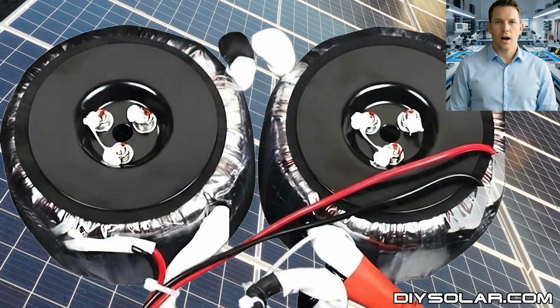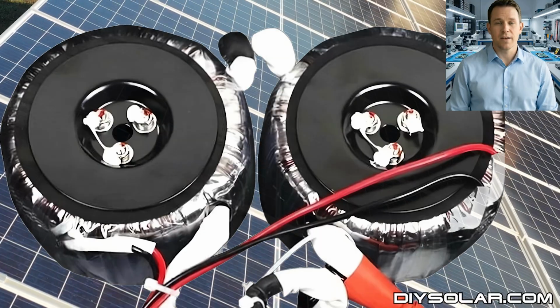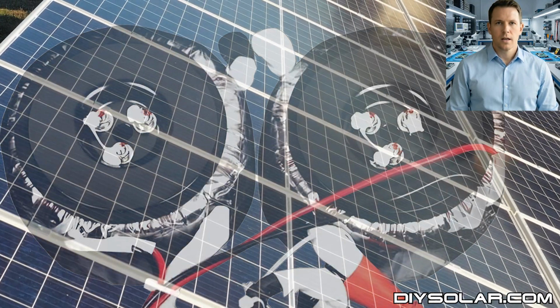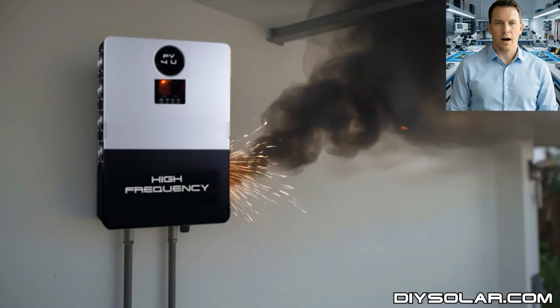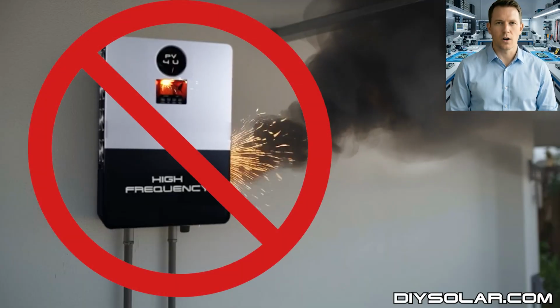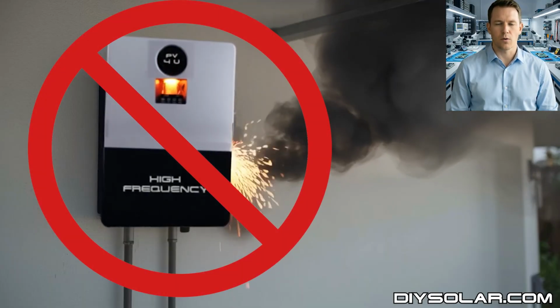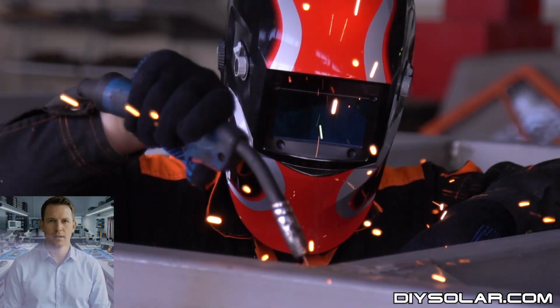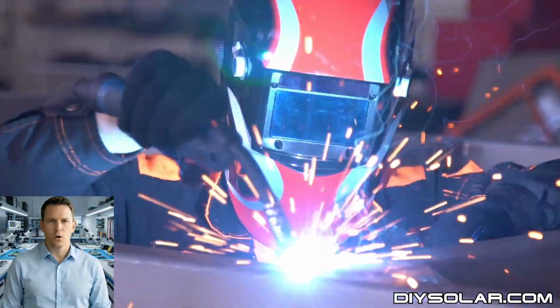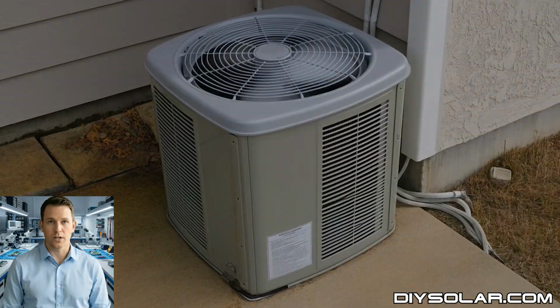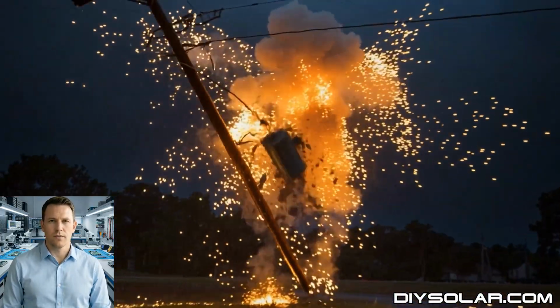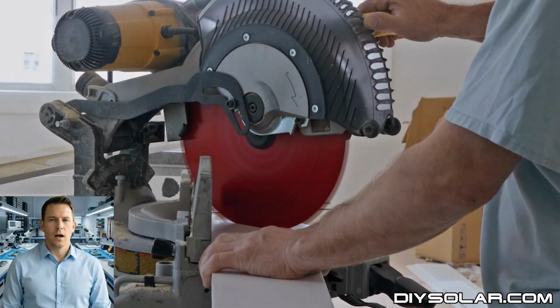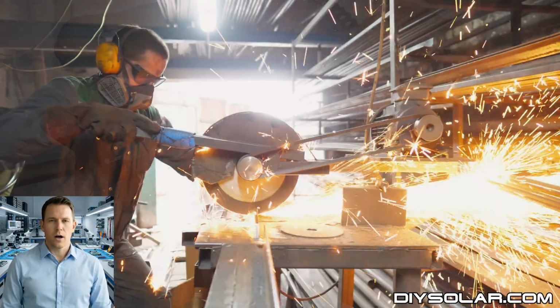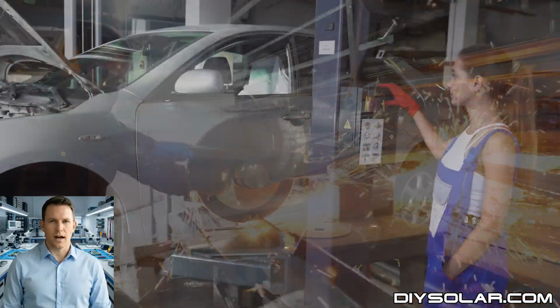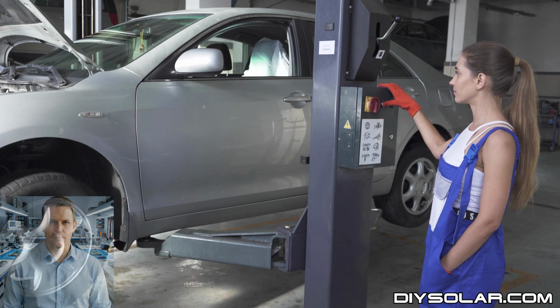Our 10-kilowatt iron core inverter is built with massive, heavy-duty output transformers, delivering real-world performance that outperforms and outlasts many of the 12-kilowatt high-frequency transformerless units everyone else is pushing. Designed for brutal surge loads and demanding 24/7 operation, it's far more resistant to failure from lightning strikes, high inrush current exposure, and punishing inductive loads than the lightweight high-frequency alternatives flooding today's market.